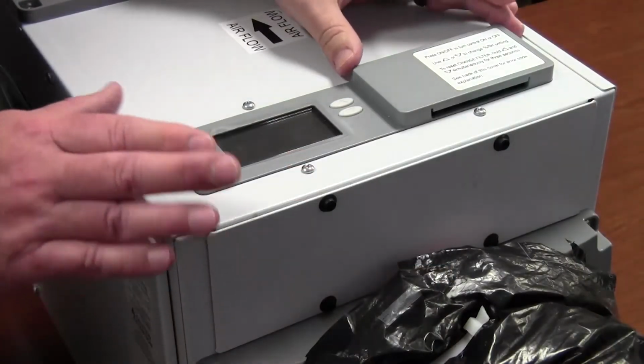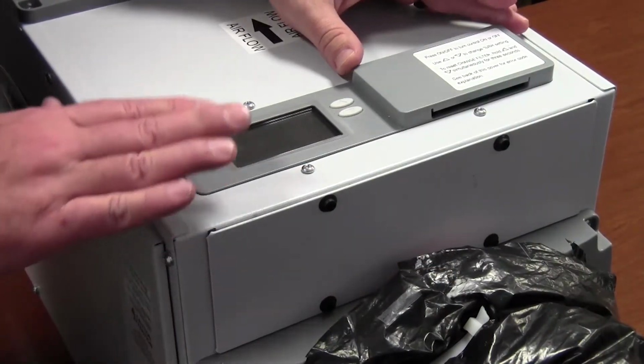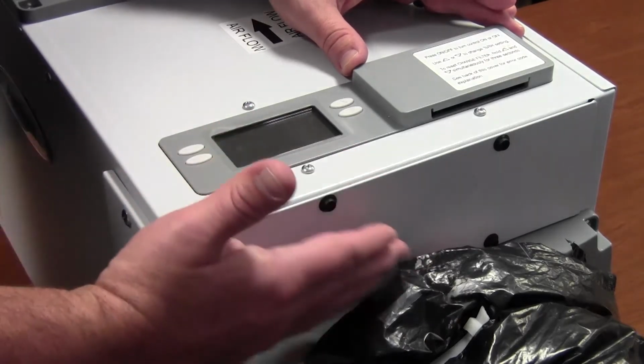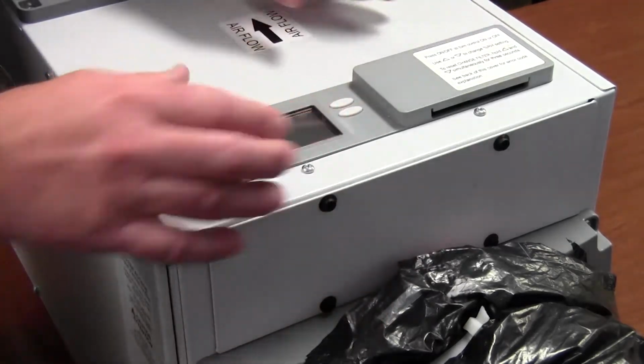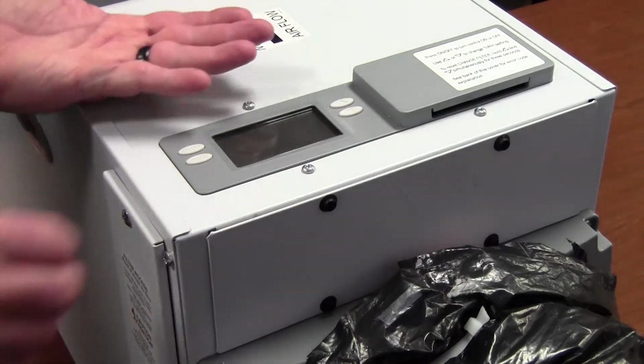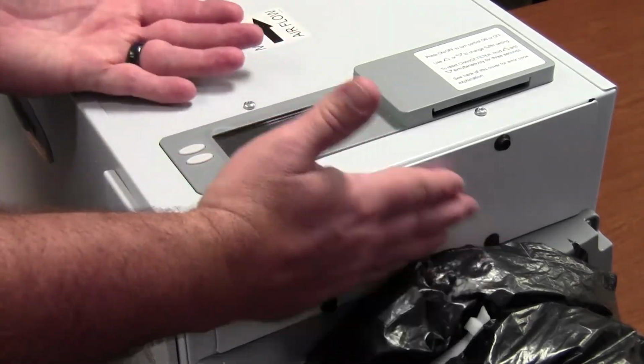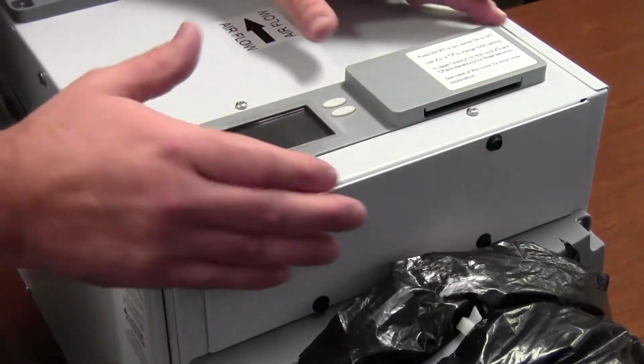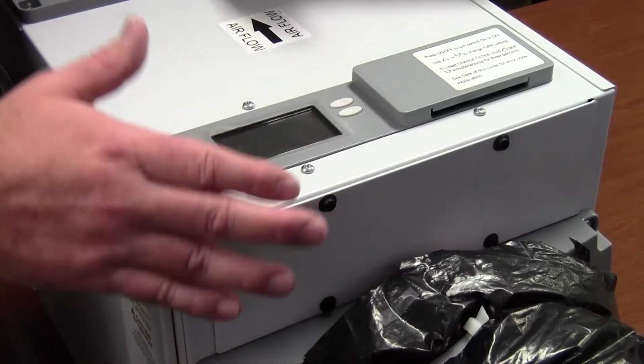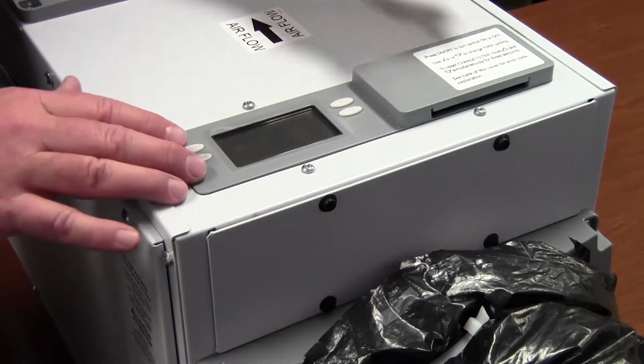All the units ship with this digital control on the top of the unit. The digital control can be moved to the front. This plate comes off, and you take the filter access door out, stick your hand in, let the control fall down on it, and remove this and just bring it right to the front and put the screws back in. So you can move it to the front if that's easier, like in an attic installation when you're up close to the ceiling, or whichever way you need it to be.